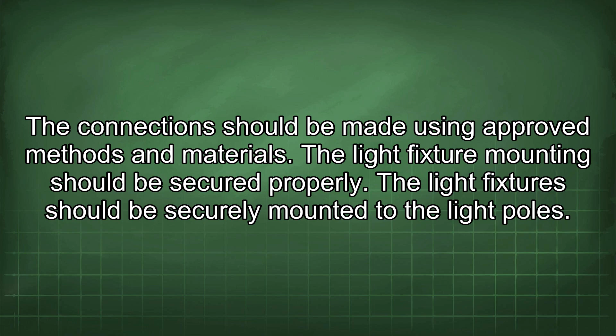The light fixture mounting should be secured properly. The light fixtures should be securely mounted to the light poles. The mounting hardware should be corrosion resistant and capable of withstanding the weight of the light fixtures. The light fixtures should be installed in accordance with the manufacturer's instructions. The photocell or timer control should be installed, if one is used.